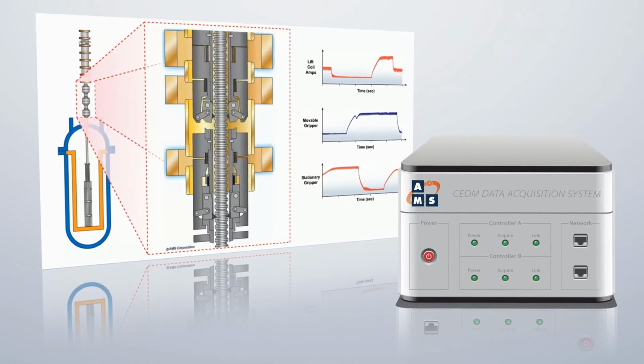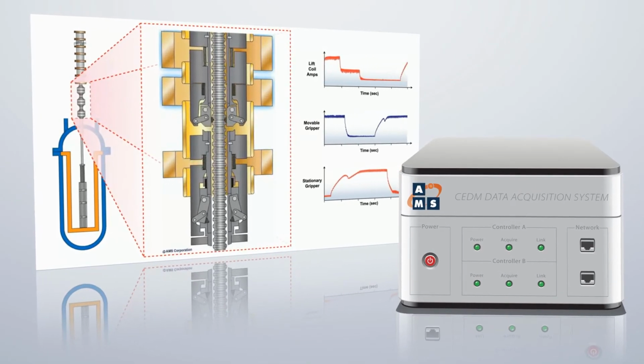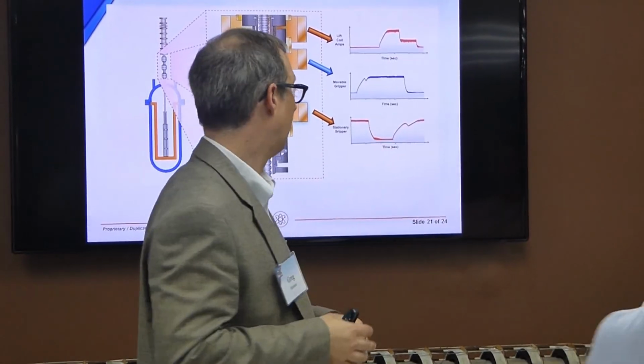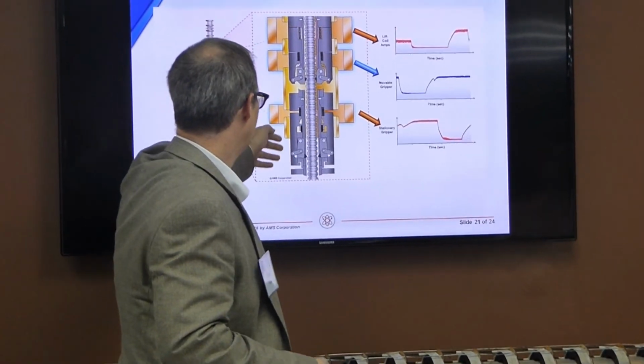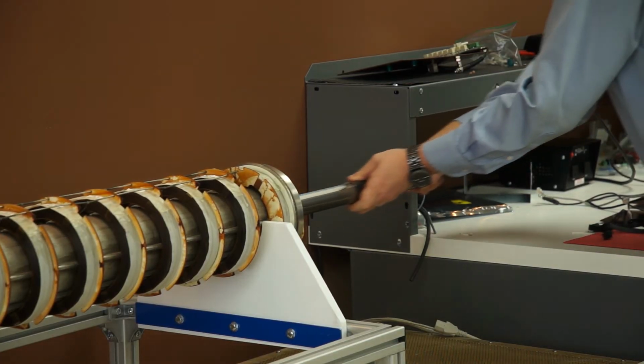With new AMS developments, rod drop time measurements can be performed on all rods simultaneously, thereby reducing test time to less than 60 minutes compared to the 12 hours or more that it takes to perform the test using conventional testing procedures.